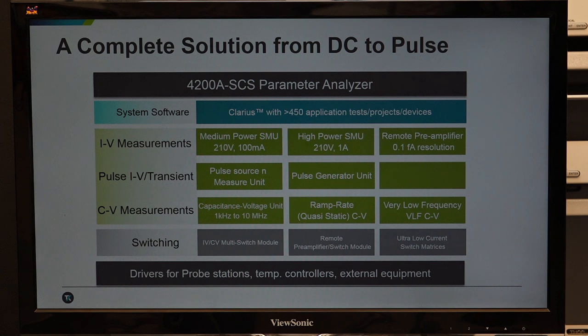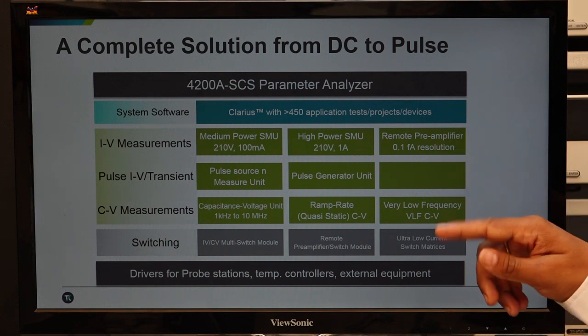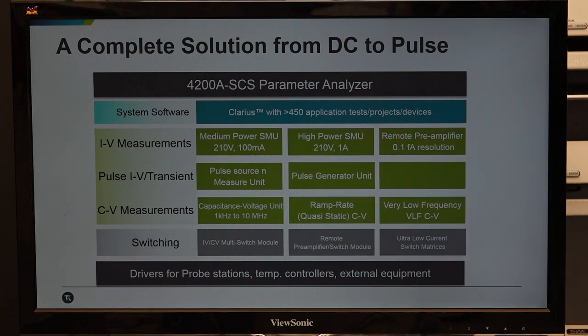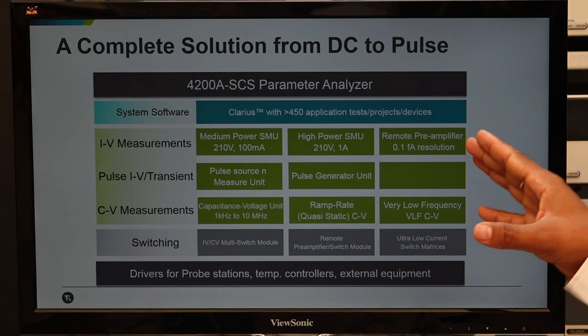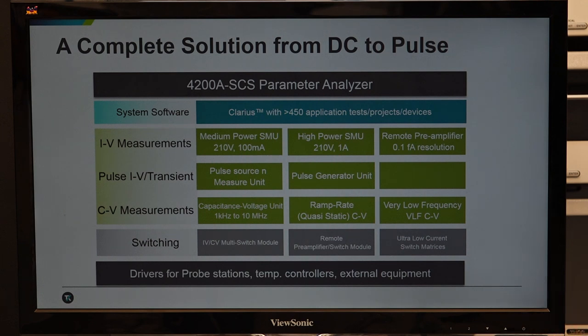Medium power SMU supports 100 milliampere with 2 watt power restriction. High power supports 1 ampere with 20 watt power restriction. For ultra-low current measurement, there is a special remote pre-amplifier attachment. Depending on how many device terminals are there, we can decide how many SMUs are required — for testing a 3-terminal device, 2 SMUs are enough since the instrument has a separate ground unit. For CV measurement, we can have multi-frequency CV or quasi-static and ramp rate CV, and ultra-low frequency CV for special devices.